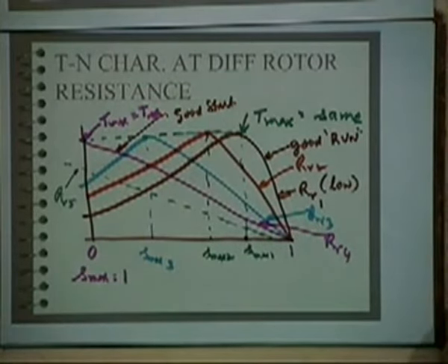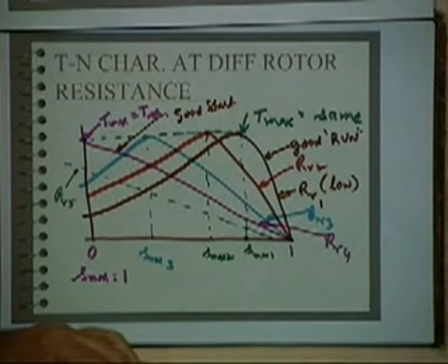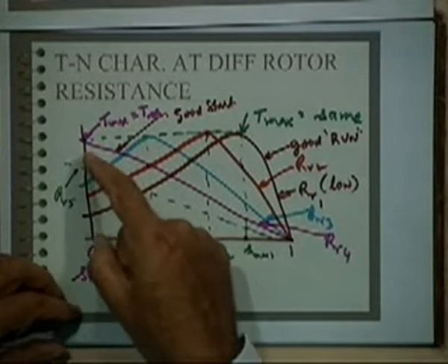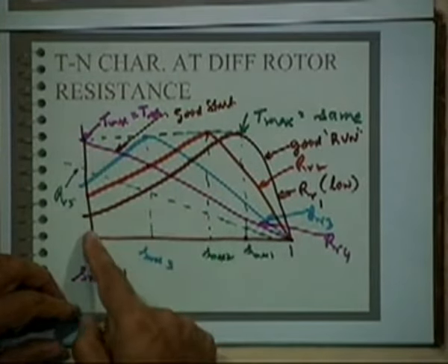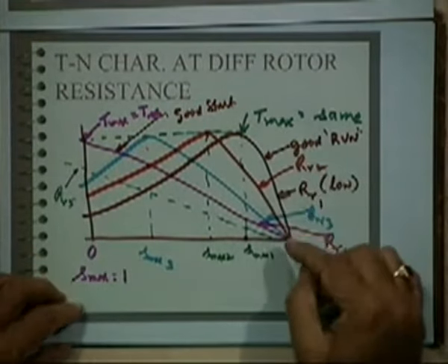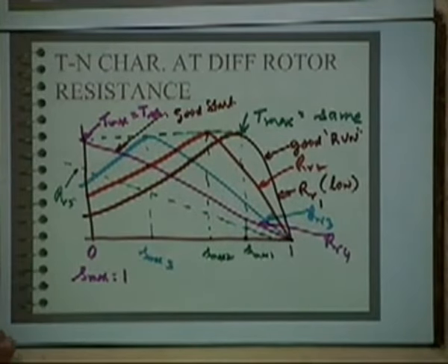Okay. Therefore, ideally you must have a varying rotor resistance, but that is not possible in squirrel cage machines generally. In slip ring machines it is possible. If you can connect an external resistance and increase the rotor resistance so that it gives you a good starting torque, and go on decreasing resistance, it comes to the running condition. So you have good running performance and good starting performance. So this is a compromise, right? So your rotor design is therefore crucial.